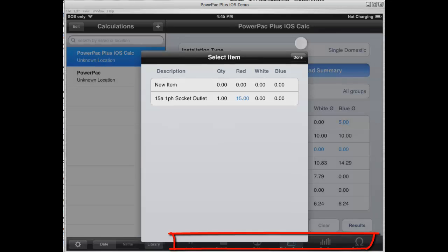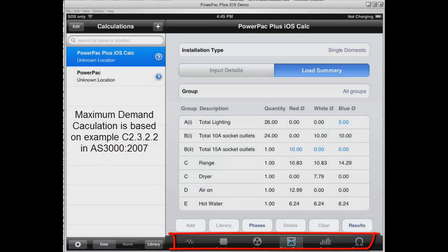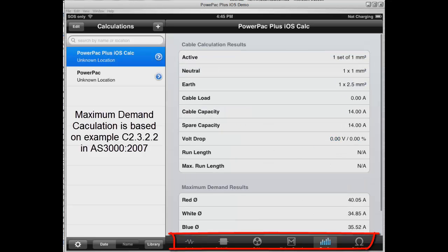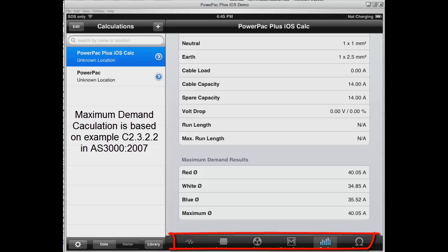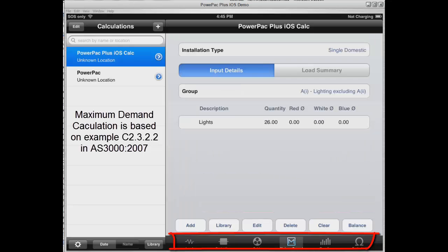We put the 15 amp outlet on red phase and the lights on blue phase — you can see they've been highlighted in blue. Once we look at the results, we can see them down the bottom under the maximum demand results, and we can see the higher rated phase is 40.05 amps.